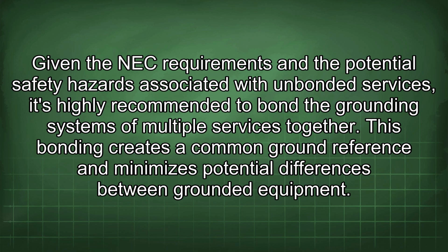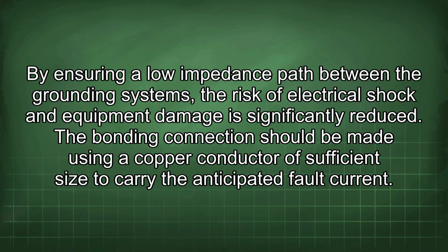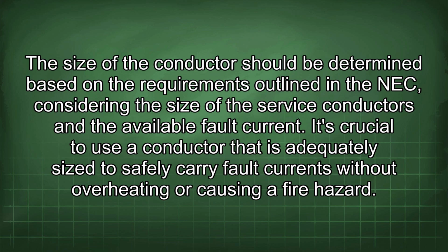This bonding creates a common ground reference and minimizes potential differences between grounded equipment. By ensuring a low impedance path between the grounding systems, the risk of electrical shock and equipment damage is significantly reduced. The bonding connection should be made using a copper conductor of sufficient size to carry the anticipated fault current. The size of the conductor should be determined based on the requirements outlined in the NEC, considering the size of the service conductors and the available fault current.